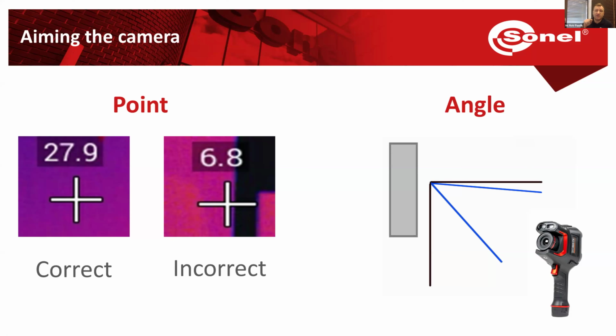The camera has certain markers, or points, but remember the point is 3 pixels by 3 pixels, covering an area of 9 pixels altogether. We want to make sure that when checking the temperature of a point, this 9-pixel area covers an area of the same temperature. If it's on the border of two different objects, you'll get an average value from those 9 pixels, and it may not be true - here on the pink side the temperature is higher, on the black side it's lower, so this reading is probably not true since half the marker is on an area of different temperature than the other half.